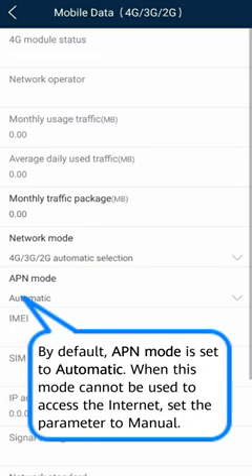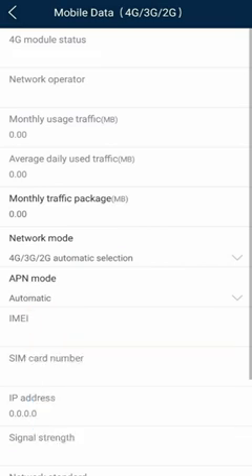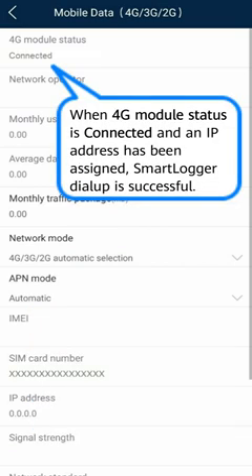By default, APN mode is set to Automatic. When this mode cannot be used to access the internet, set the parameter to Manual. When 4G module status is connected and an IP address has been assigned, SmartLogger dial-up is successful.